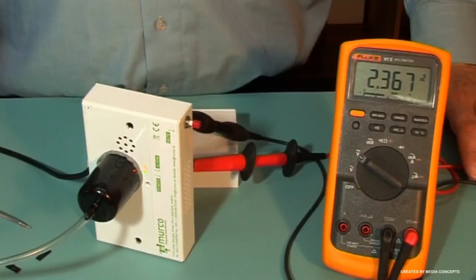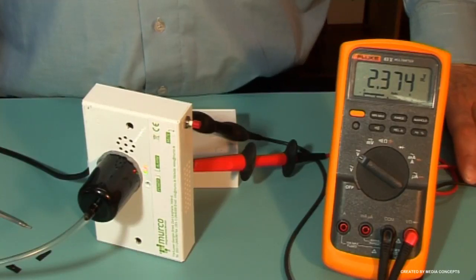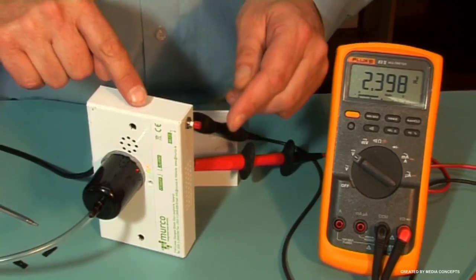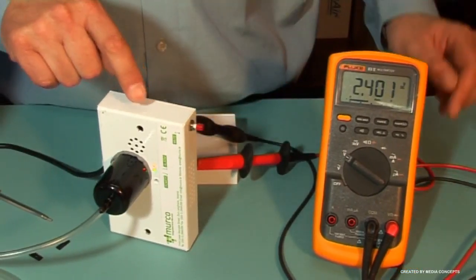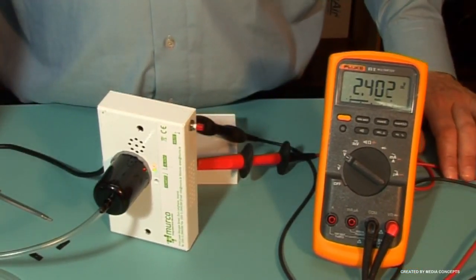The relays should also activate, and if the IAM is connected to the remote IAM-C panel, then this should also display the red light from the alarm on the panel. The IAM sounder can be muted by pressing the red mute button. If connected, the IAM-C can be muted by turning the switch.